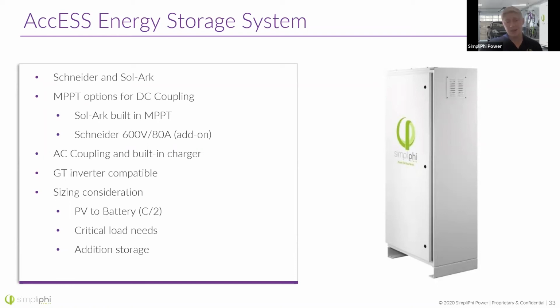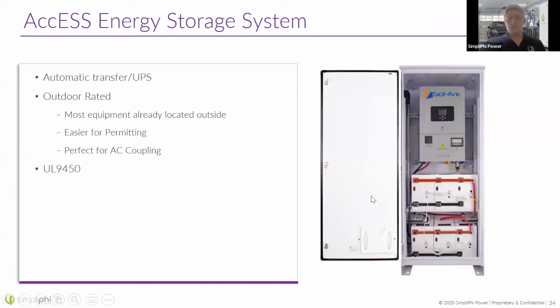Keep in mind sizing considerations again for an AC coupled system, a little bit easier to oversize a DC coupled system. They are going to have an automatic transfer switch, so they will operate fully as a UPS with the extremely low transfer time. It's so fast that even your sensitive electronics will not know the power went out. So we're talking about transferring from relying on grid power to then switching over to relying on inverter and battery power. It happens in a matter of a small fraction of a second.